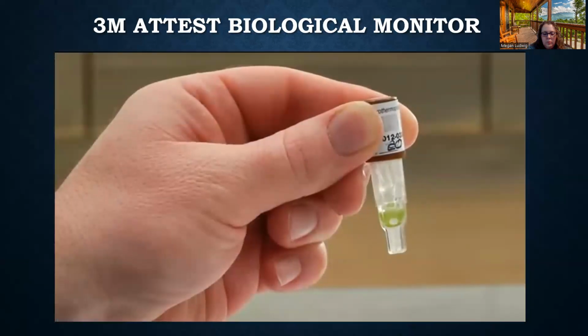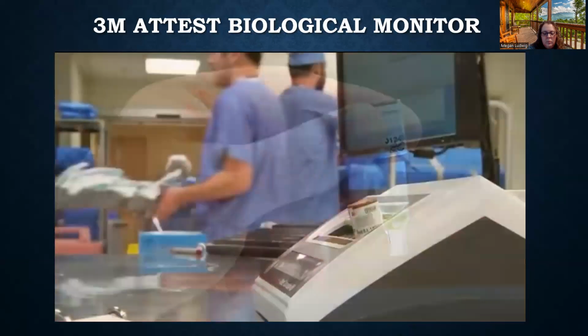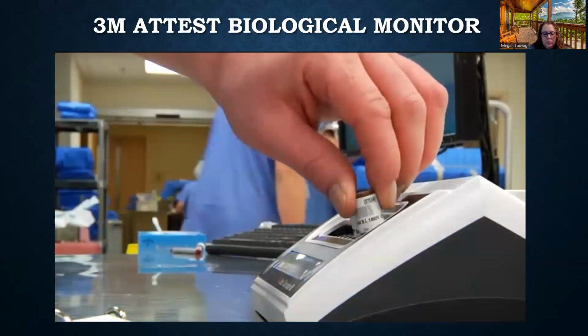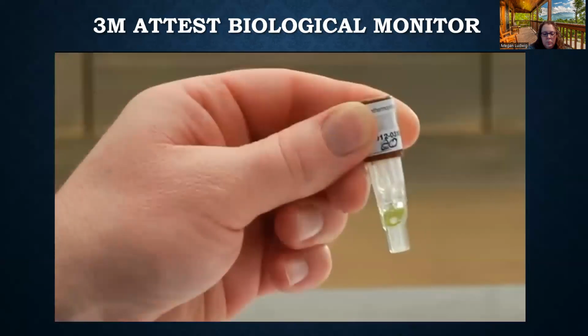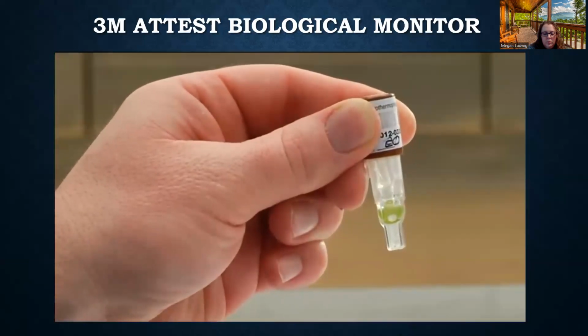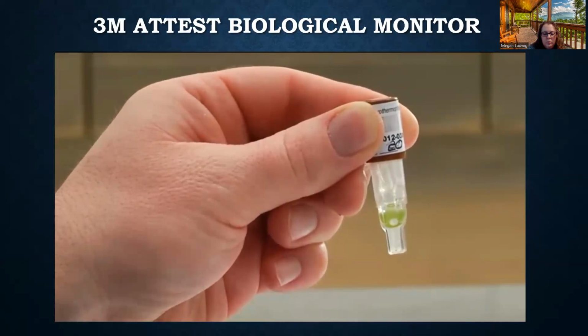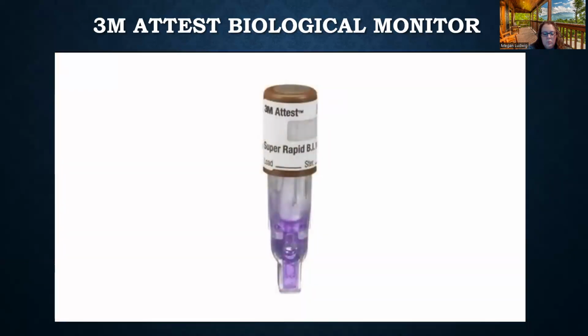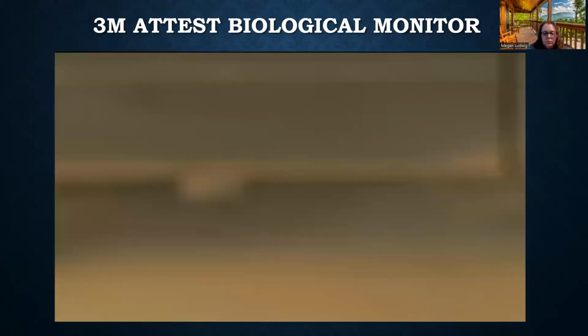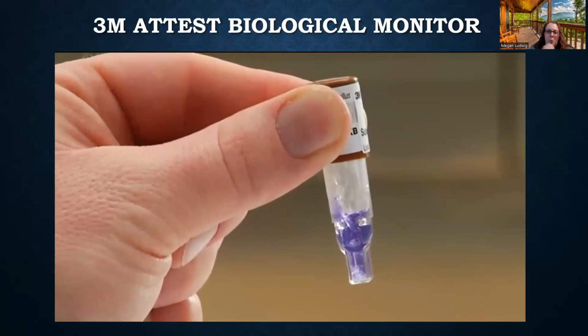Any evidence of yellow color within the vial indicates a positive result. In the case of a processed 1492 VBI, a color change from purple to yellow of the growth media and/or nonwoven material indicates a sterilization process failure. A negative pH color change result, where the media and nonwoven material remains purple or blue, can be assessed after 48 hours of incubation.